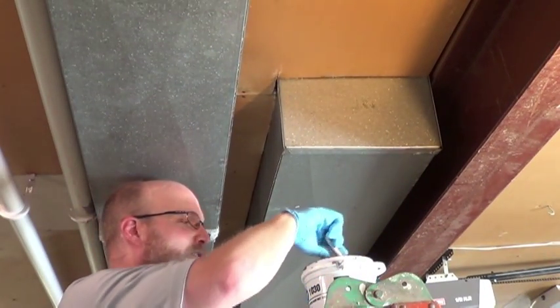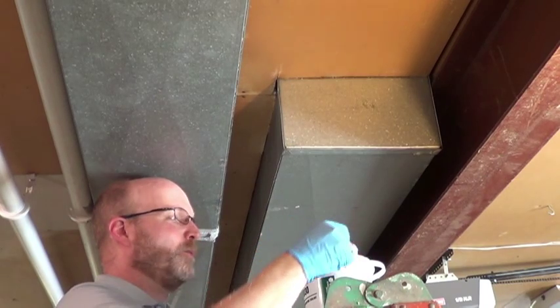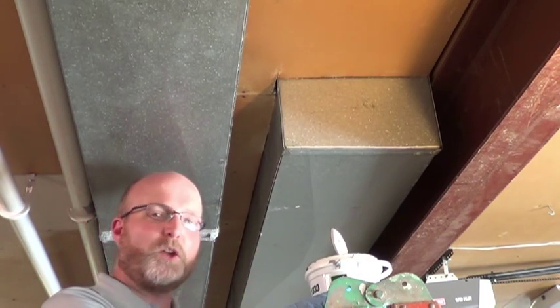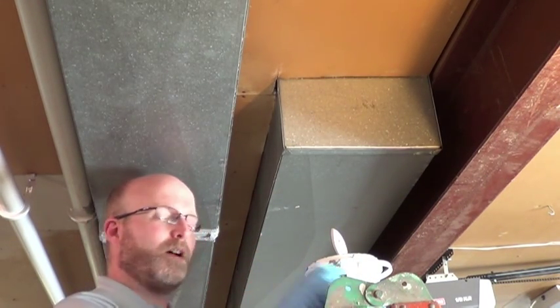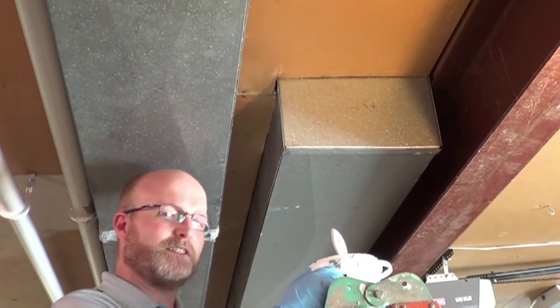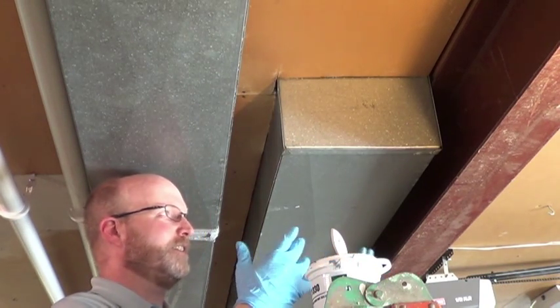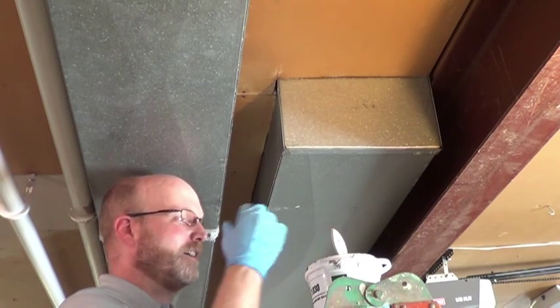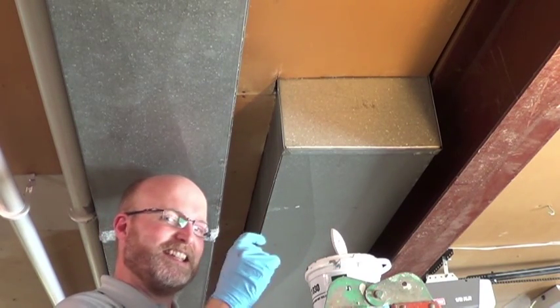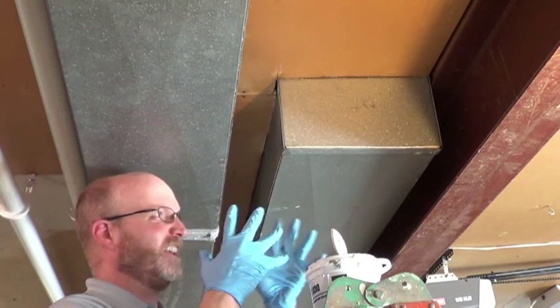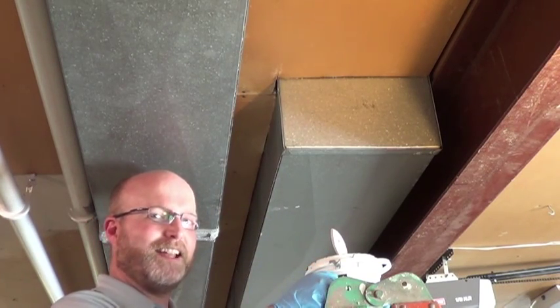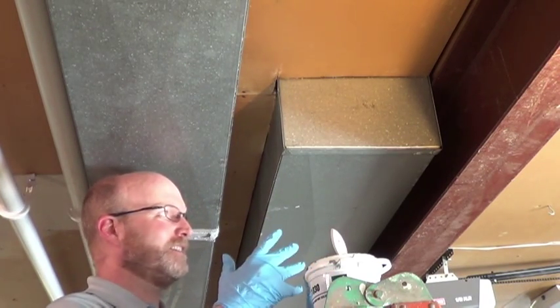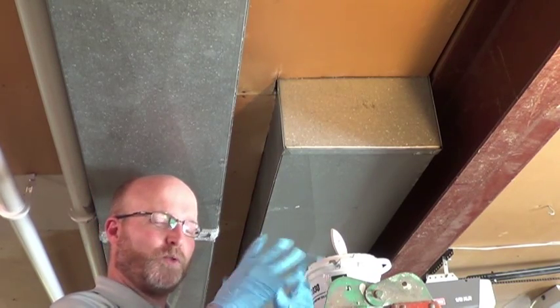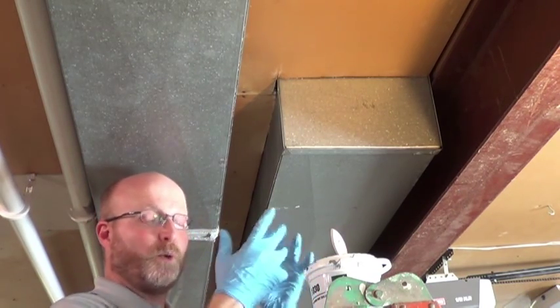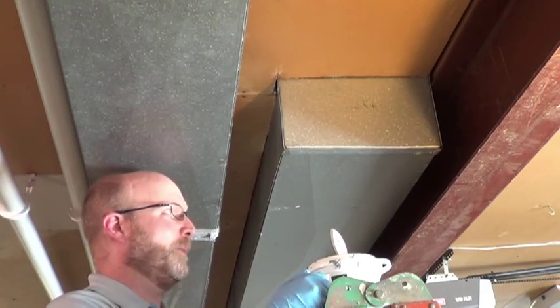Alright, so we're going to seal some ducts. When you use duct mastic, most important thing to remember is you lay it on pretty thick. Some people call it painting ducts. I would not call it painting ducts because when we paint walls and ceilings, we paint that pretty thin. Duct mastic should be applied as thick as a nickel. Think of it as like a liquid caulk. We want to make sure it gets a nice tight seal. And with that thickness, it can withstand the expansion and contraction of the ducts over time, as you of course heat or cool, either or.